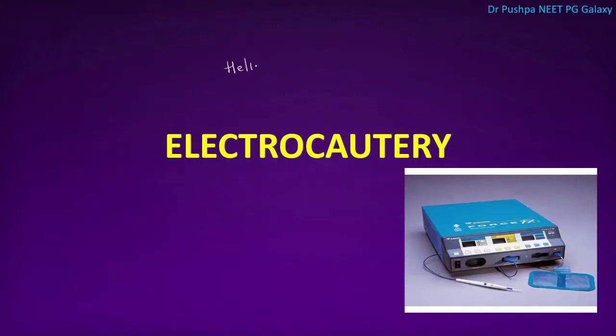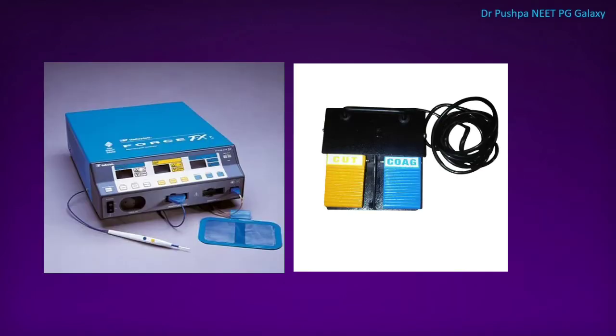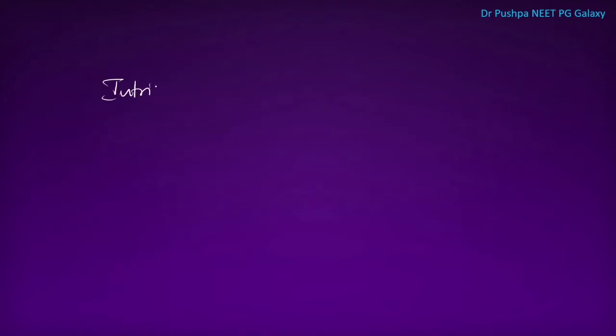Electrocautery is a method to achieve hemostasis and to cut tissue during surgery. It uses the intrinsic thermal effect of high frequency electric current. Cautery can be used for coagulation or cutting.